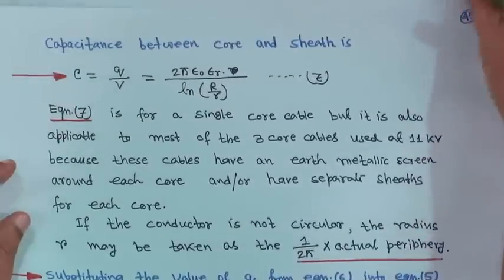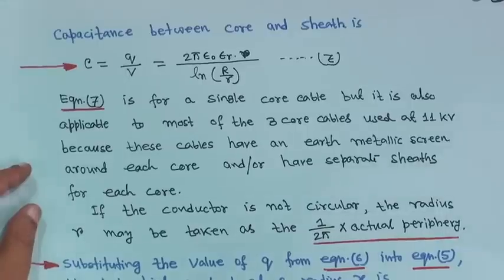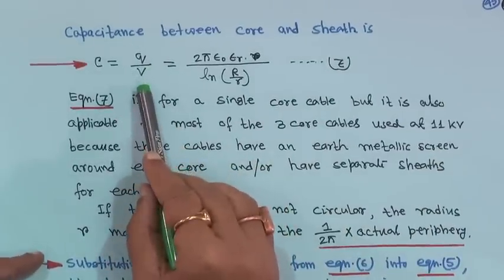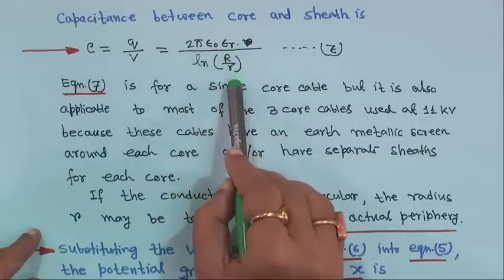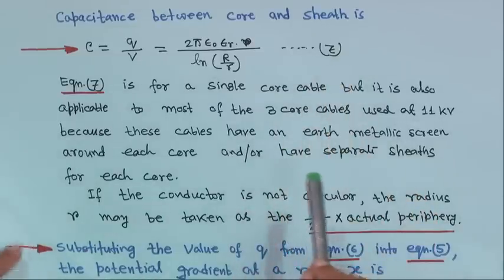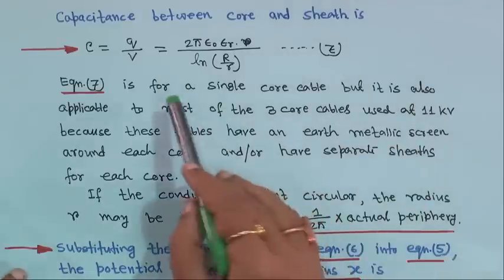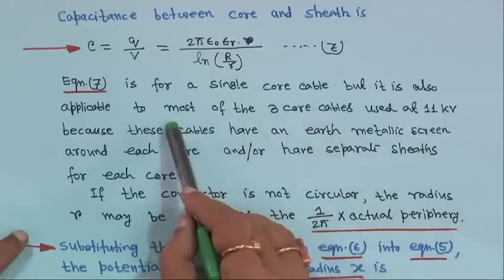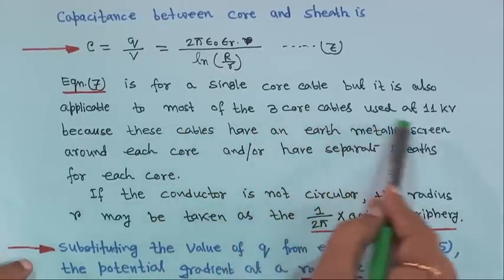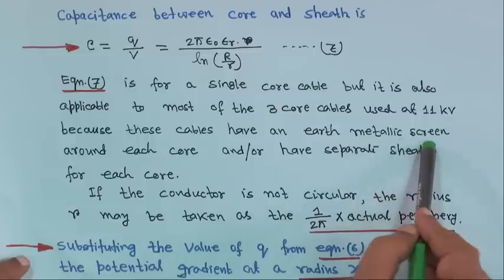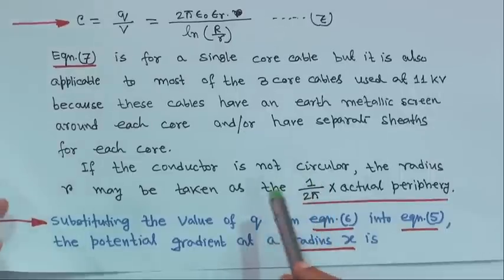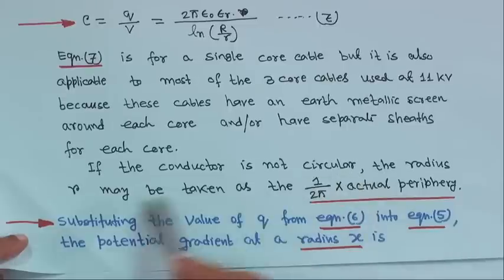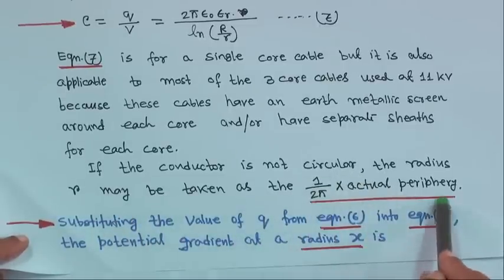Therefore, capacitance between core and sheath is C = q/V = 2π ε_0 ε_r / ln(R/r) — equation 7. Equation 7 is for a single core cable, but it is also applicable to most 3-core cables used at 11 kV, because these cables have a metallic screen around each core or have a separate sheath for each core.